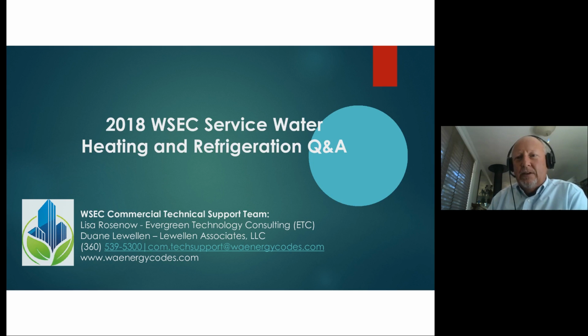It's primarily come up in terms of the hot water heating set point, but my reply to that is this language for demand response on the larger electric tank type water heaters is actually straight out of the IECC, which is vetted at the national level by the ICC. I would assume if there was a conflict with the International Plumbing Code or any other health and standard codes, including NSF, that would have been addressed. I've heard about Legionella in terms of set points for water heating systems, but I haven't heard about it from demand response.